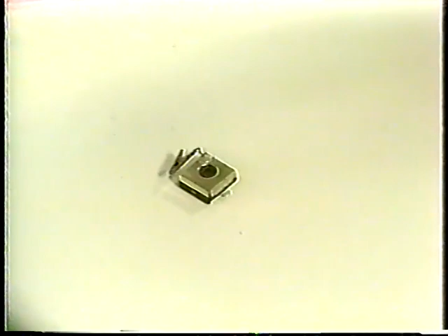So now we're going to try a Faraday cage foil-containing laminate bag, as we are required to use. And I'm going to put the static event detector inside of it, slide it in there. Okay, now I'm going to remove my wrist strap, and I'm going to try real hard to trip the detector by touching it. Okay, and now we'll empty it out of the bag. And if you'll zero in, we'll see that it has not been tripped in this case. The Faraday cage bag has protected it.